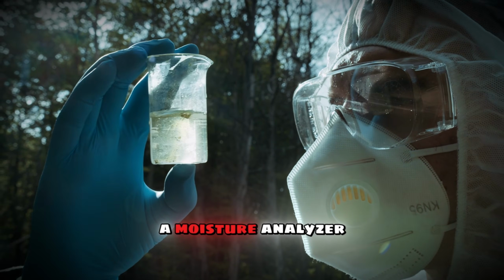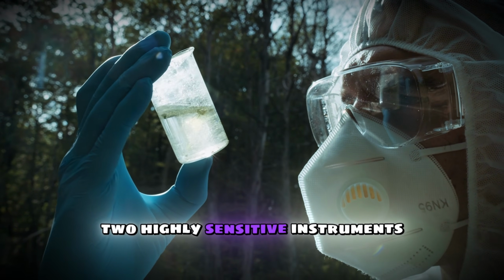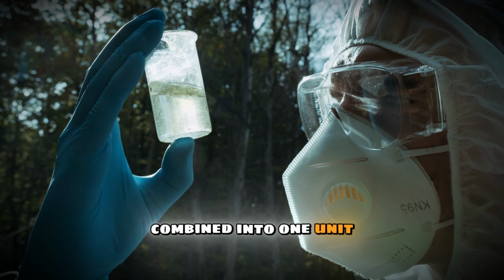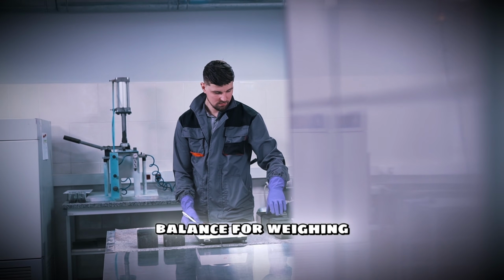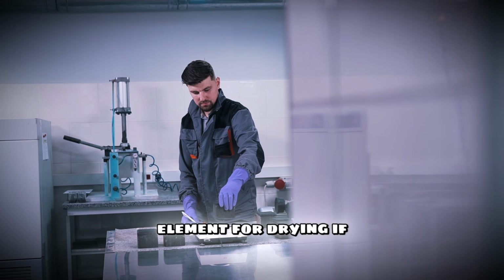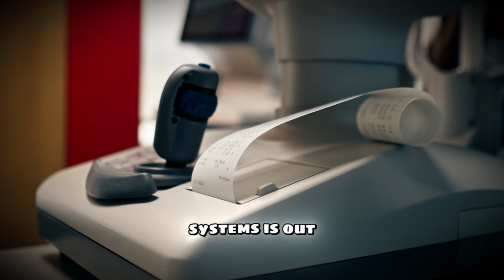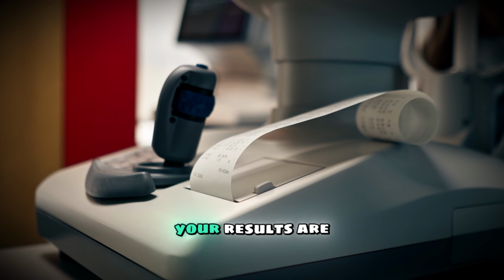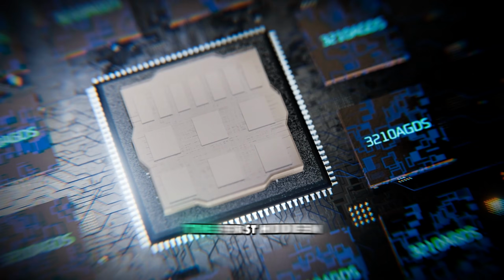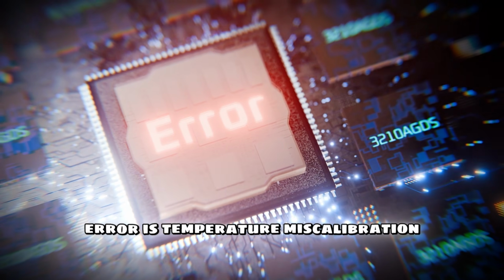A moisture analyzer is essentially two highly sensitive instruments combined into one unit, a precision analytical balance for weighing and a heating element for drying. If either of these systems is out of calibration, your results are completely invalid. The first hidden error is temperature miscalibration.